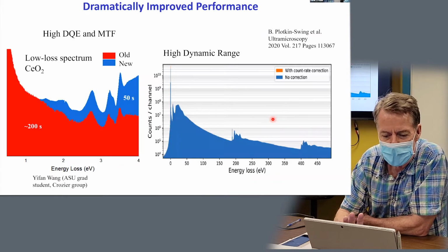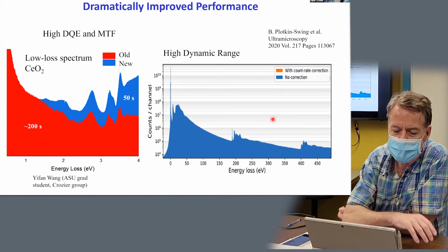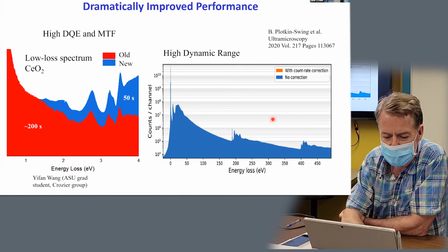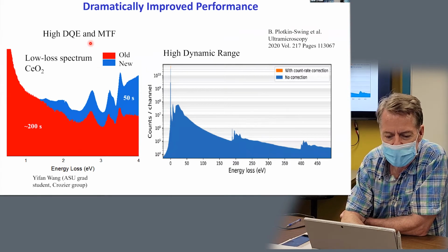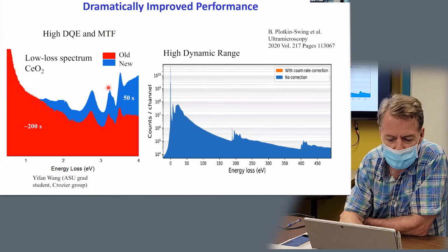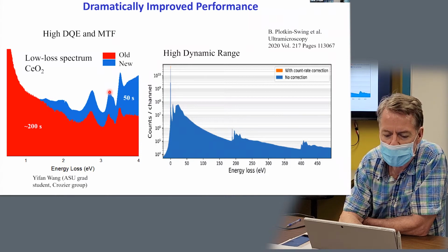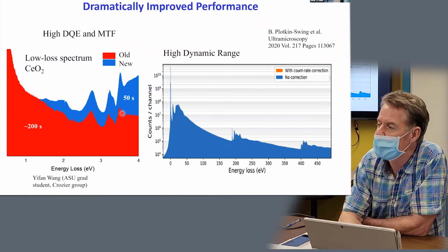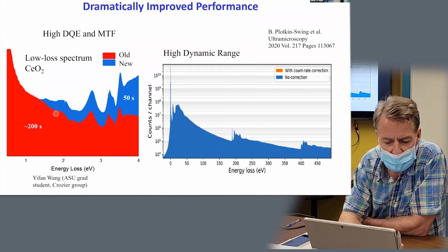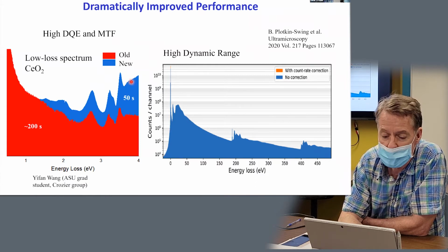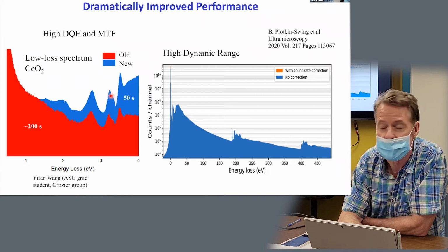Just to show you some practical things, and Shize will show you more examples, but in terms of electron energy loss spectroscopy, this is an example that illustrates the improvement in the sensitivity, the improvement in the DQE, and in the point spread function. So this is a valence loss spectrum from cerium oxide, showing photonic modes. The band gap is about here, and these are photonic modes that you can see. The red spectrum was recorded with the old detector, and you can see that it's noisy. It took 200 seconds to record. The blue curve is recorded with the new detector, and you can see that it's a lot less noisy and the acquisition time is less.